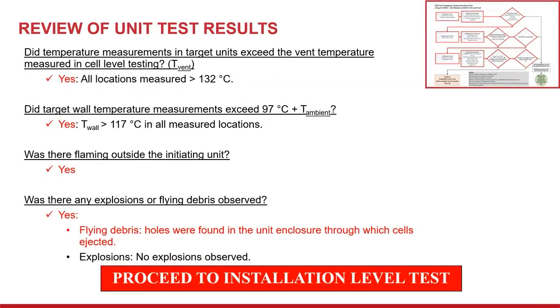During the unit level test, as we went through our assessment, we reached thermal runaway and it was propagating. We did not contain it to the unit. So the next step in the recommendations within UL 9540A is to evaluate the installation situation. What type of fire protection strategies will you use? A clean agent system? A sprinkler system? What flow rate will you use with that sprinkler system? Are you incorporating ventilation?